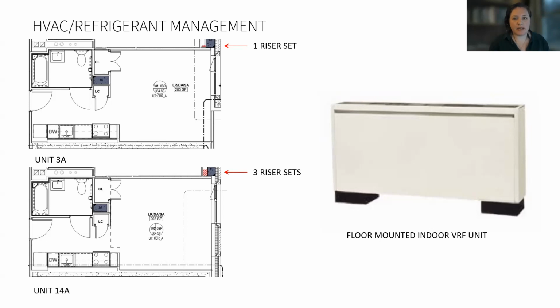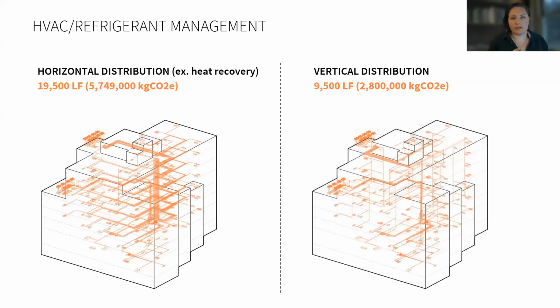So the units will be in either heating or cooling mode and not both at the same time based on facade exposure. This avoids horizontal distribution or a heat recovery setup, which would allow for heating and cooling at the same time, but uses massively more refrigerant and places refrigerant in enclosed ceilings, horizontal distribution, where it's difficult to find leaks again. This diagram is from another project, but it shows just how much refrigerant is really saved in a non-heat recovery scenario. Given the fact that refrigerant has a very high global warming potential, the ones being used now are several times more global warming potential than CO2.